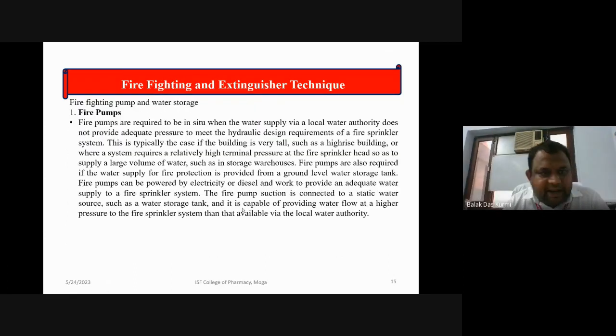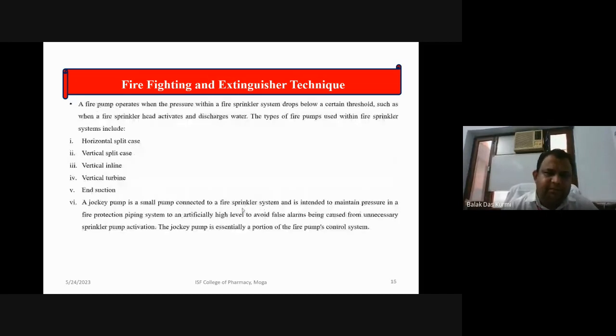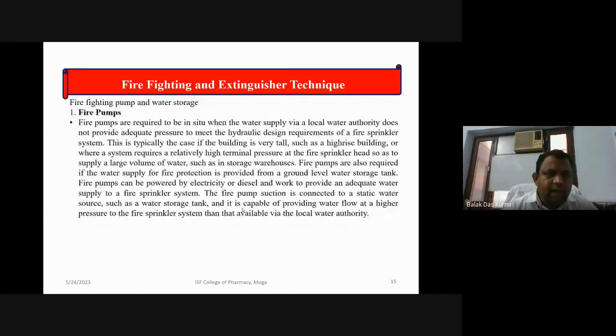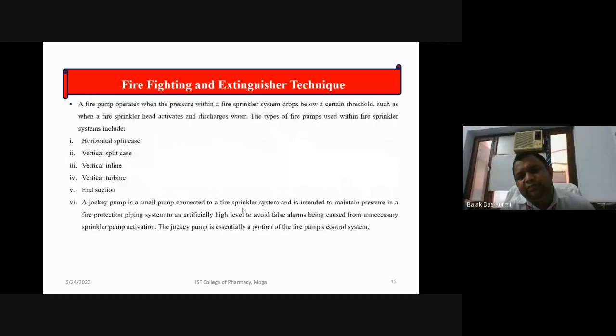Firefighting and extinguisher techniques. Although this topic is unrelated, some types of small fire pumps are required to be in situ when the water supply by a local authority does not provide adequate pressure to meet the hydraulic design requirement of a fire sprinkler. A fire pump operates when the pressure within a fire sprinkler system drops below a certain threshold, such as when a fire sprinkler head activates and discharges water.